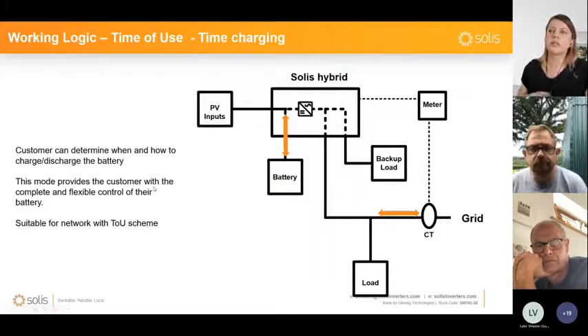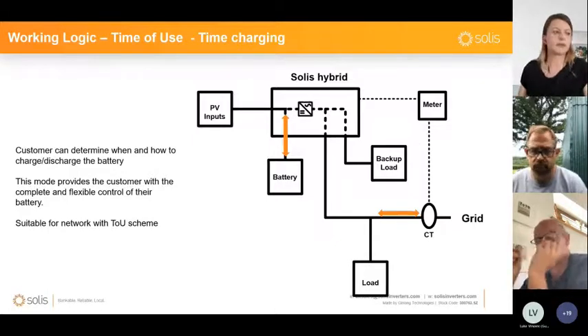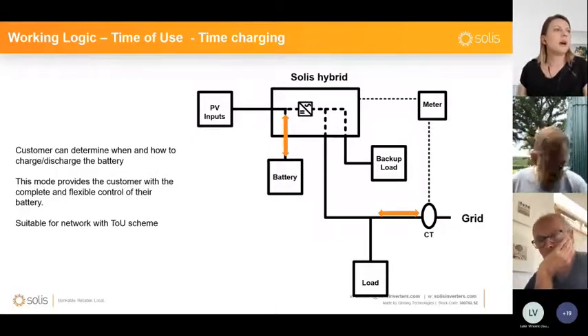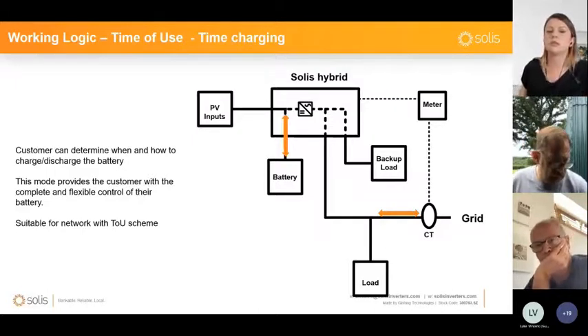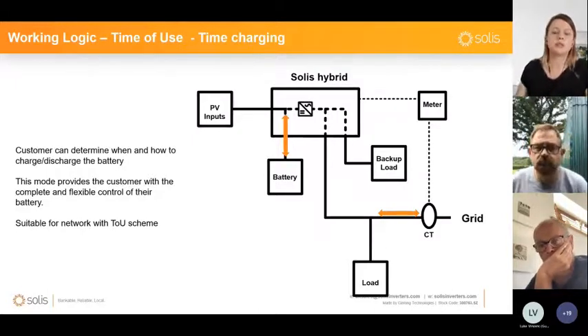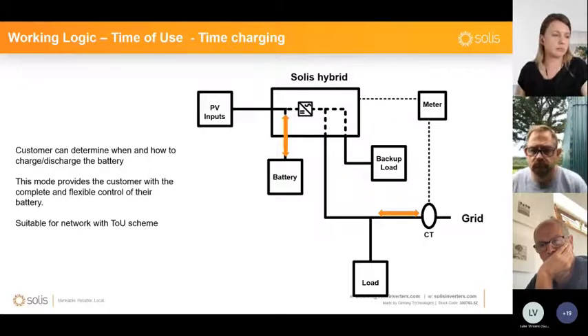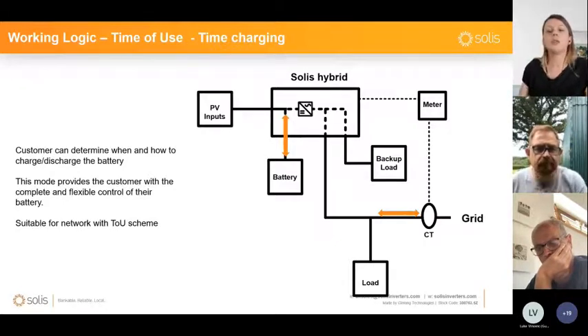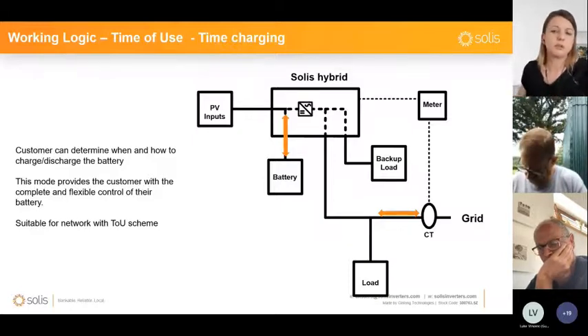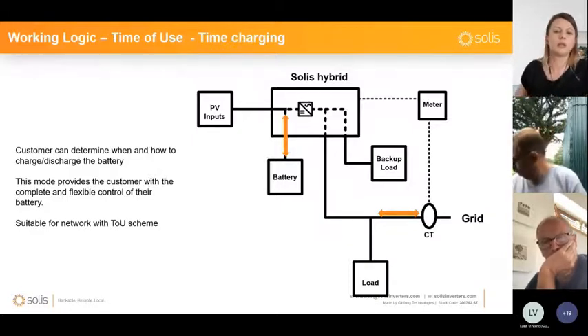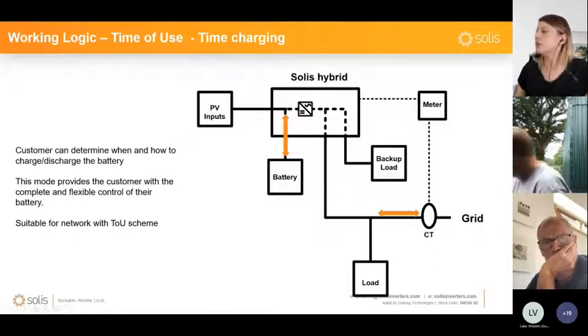This working mode is 100% compatible with the self-use mode, because, for example, you can set up the battery to be charged from 12:30 in the night down to 4:30 in the morning. And during the rest of the period, the system will work in self-use mode, and it will charge and discharge the batteries just based on the PV generation and the grid consumption.